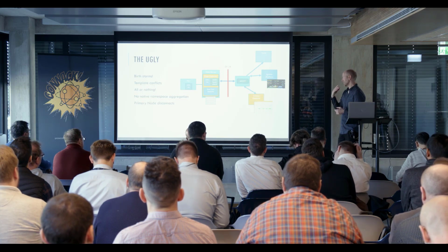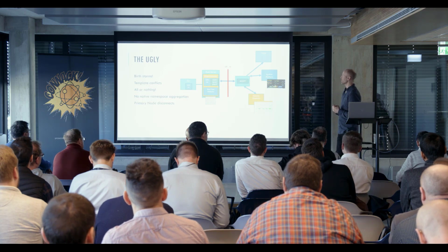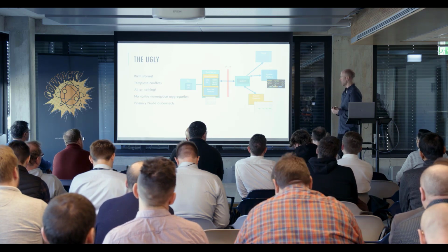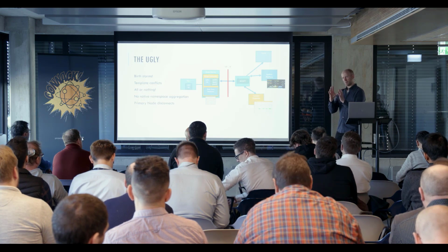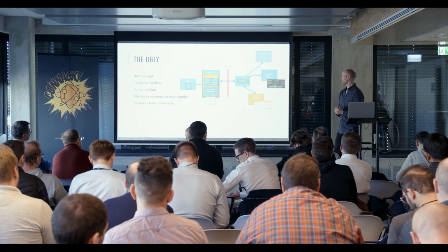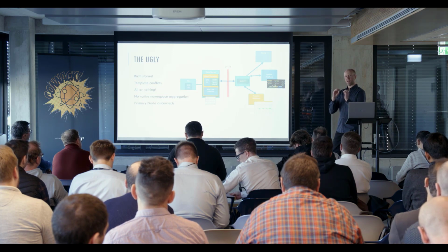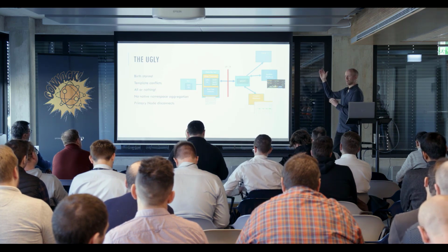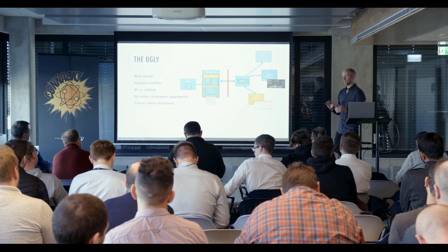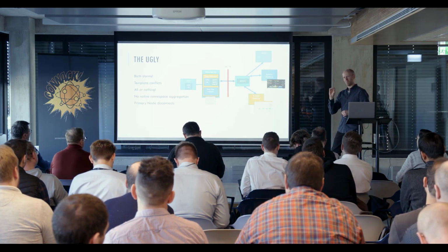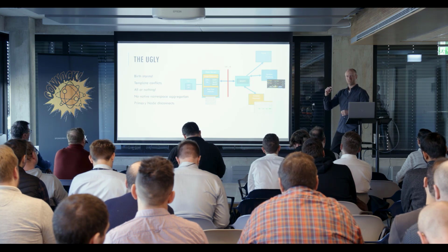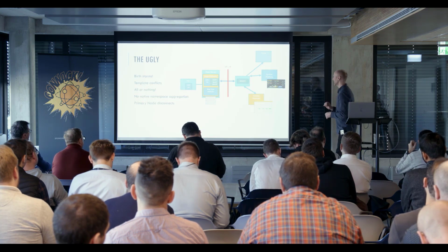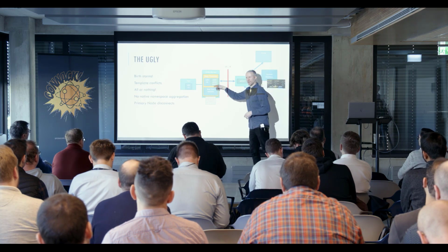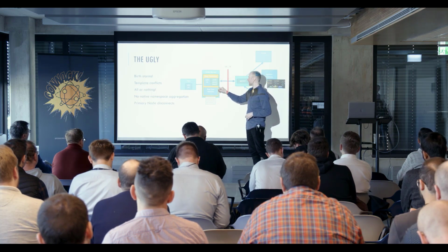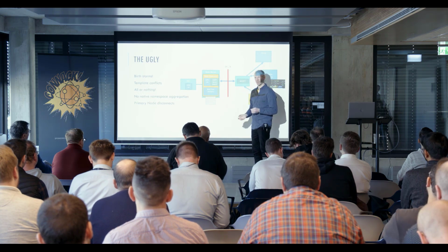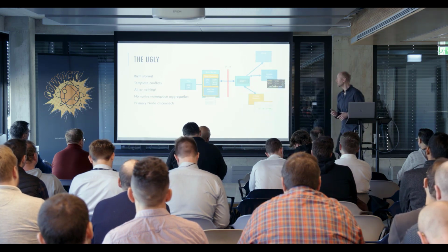A third thing, related to unified namespace, is that there's no native namespace aggregation - meaning the Sparkplug namespace of an edge node is the namespace, and I can't add to that namespace later as I move up the stack, not natively. What we do is add memory tags that we write to using the D command, if you want the details. We can add context, but not dynamically - we have to add that in the gateway before we can write to it. So it's not dynamic.